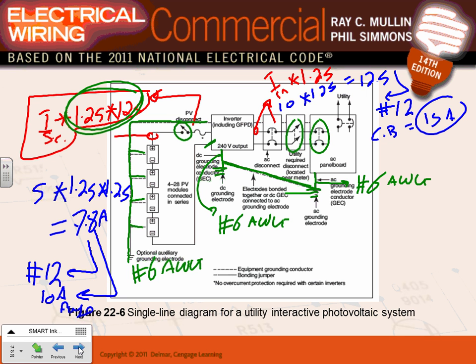Any comments, any questions? This is where the Xcel comes in. See, this is your 100 amp, and you say you're going to put a 20 amp and tie your house into the grid. You backfeed the 20 amp circuit breaker, and the circuit breaker acts as your disconnect, approved, or you put a disconnect outside. Any comments, any questions, guys, about how the system is tied to Xcel and how do we size it?